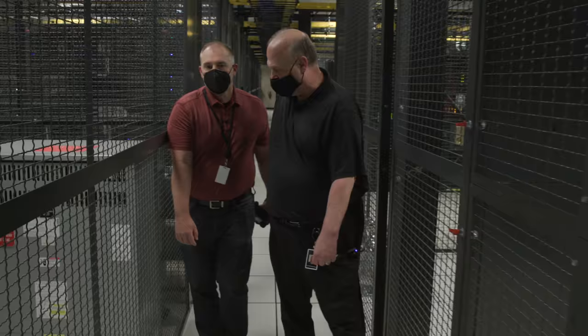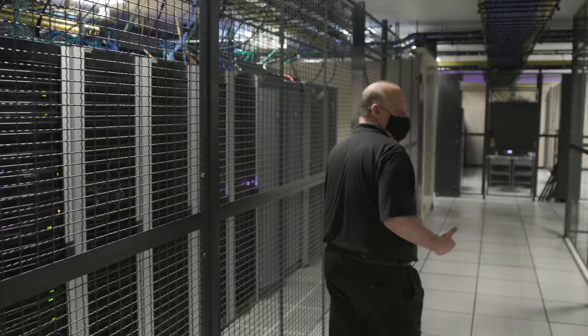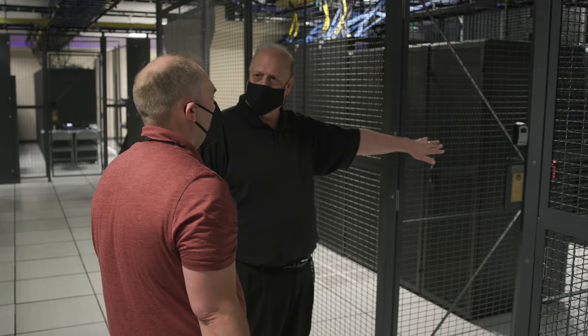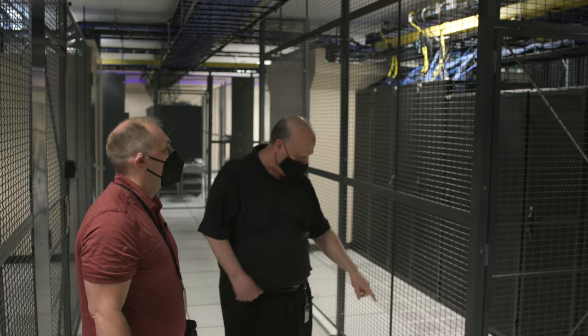What's the maximum rack height you support? There are 48U's in here — I think some are 52U. They went 10 feet; it's 10 feet from the floor to the ceiling. Most of the ones I see are 42U's. We have various sized cages on the floor and we don't constrict customers to a pod. This customer here is a payment processing customer, so they require two-factor authentication for PCI purposes. To get into their cage, you go through front security, then the man trap with iris scan, PIN, and badge, then another PIN and badge. This is a full cab capped to the top, and it also extends underneath the floor — if you raise the floor tile you can't get into that cage.